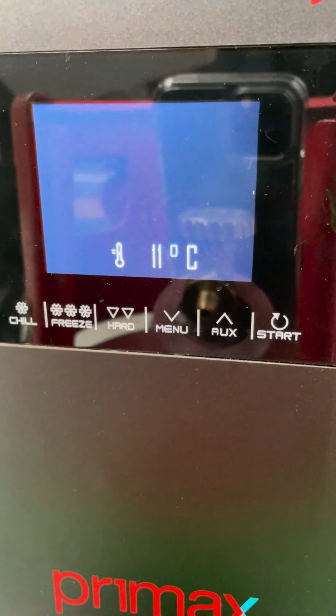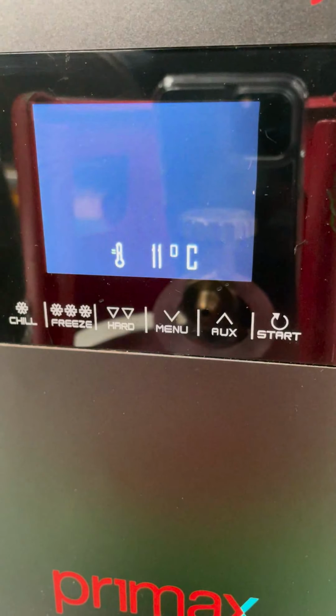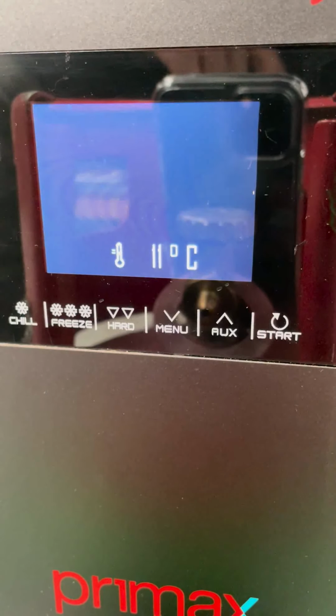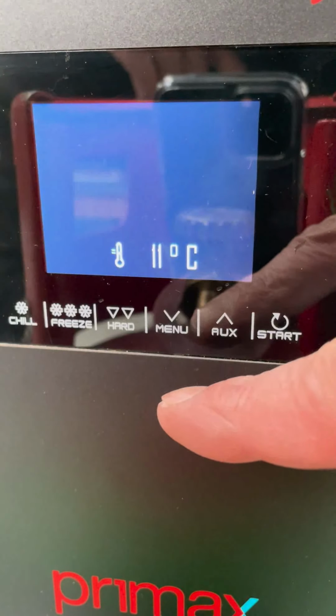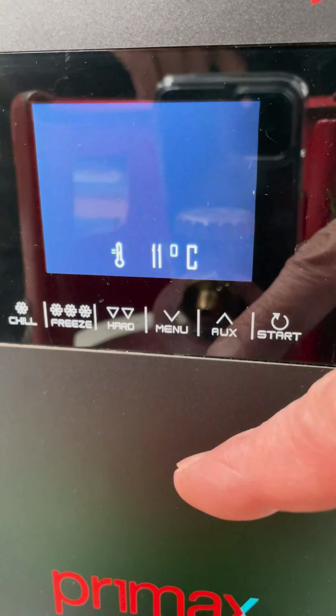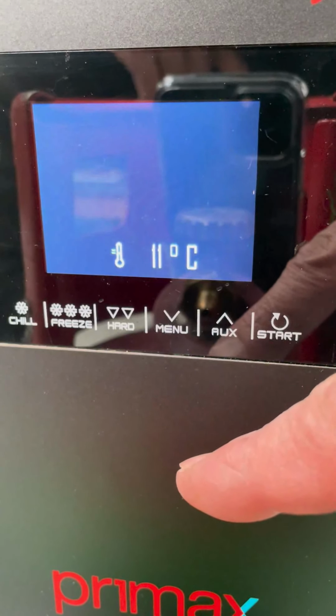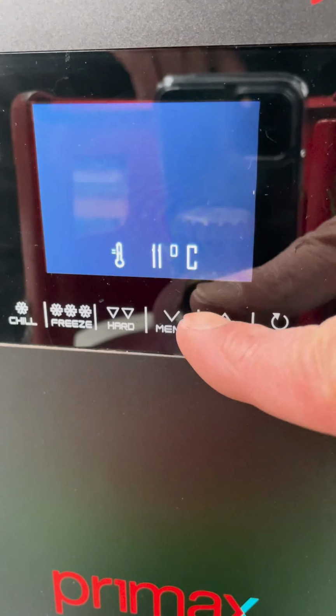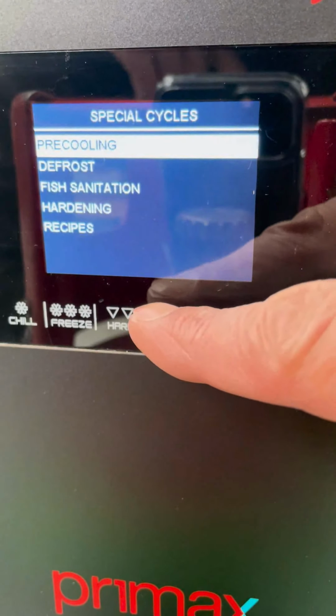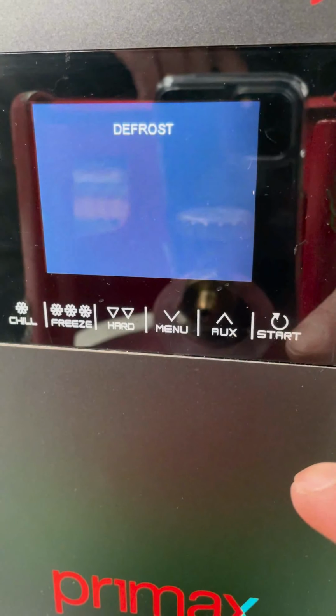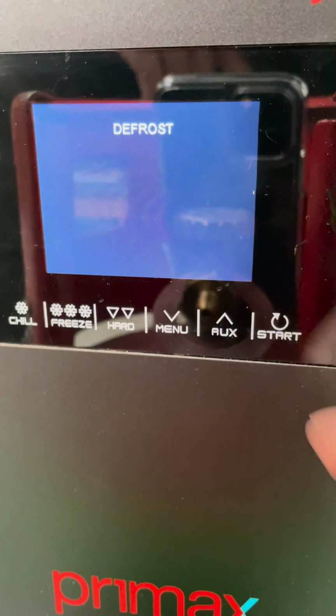Very easy. So as you see, the logic is exactly the same. So switch on the machine, pre-cool the machine, use blast chilling or shock freezing, run all the cycles you need. Certain point of the day, if the room is very humid, if you run many cycles and you see frost on the evaporator, you run a defrosting cycle. Again, aux, defrost, start, and the machine will run the defrosting cycle.